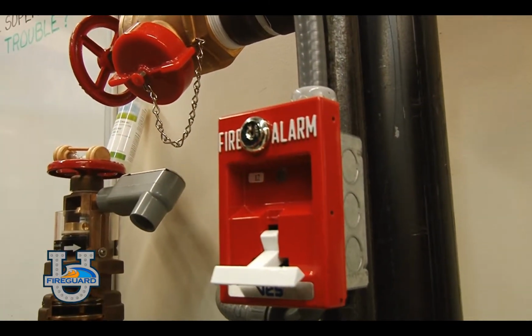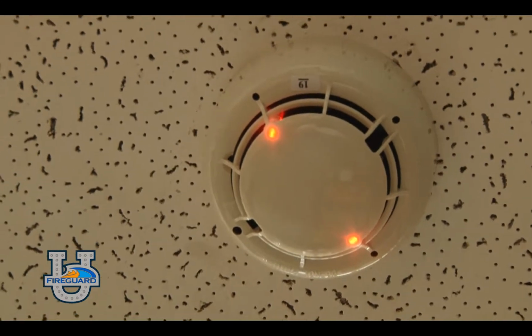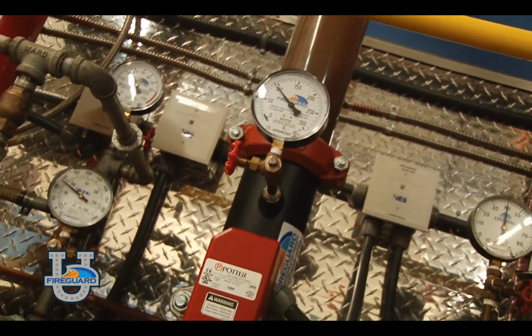Common examples of fire devices are a manual pull station, a smoke detector or sensor, a heat detector or sensor, the water flow switch. It reacts to a flow of water in the fire sprinkler pipes following a sprinkler head activation. The second category of event on your fire alarm panel is a supervisory.